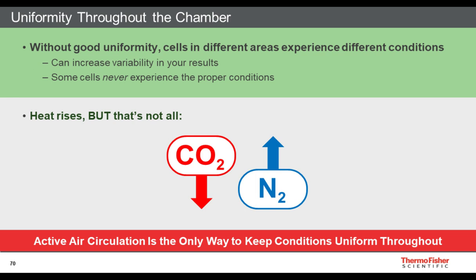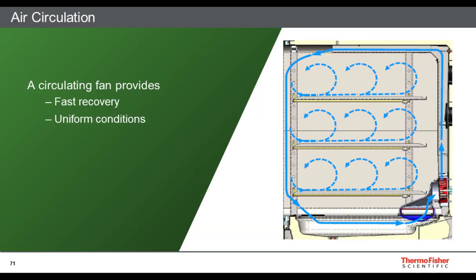So without a circulating fan, you can have stratification of conditions inside an incubator such that cells at the top will experience very different conditions than cells at the bottom. And if you're doing a large production, or a large experiment in R&D, you will have cells in different conditions depending on where your culture vessel is in the incubator chamber. So the only way to ensure that you have uniformity throughout the chamber is to use a circulating fan.